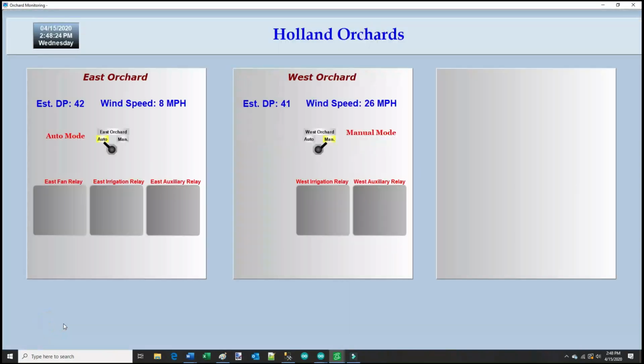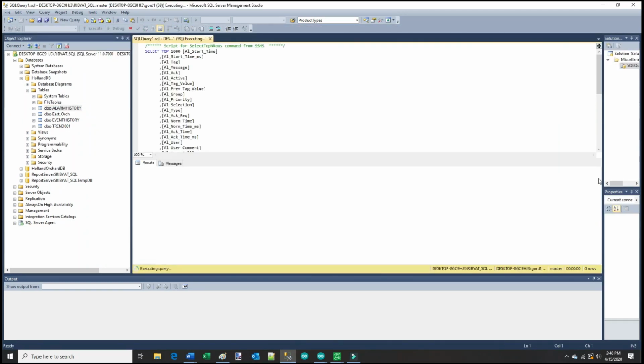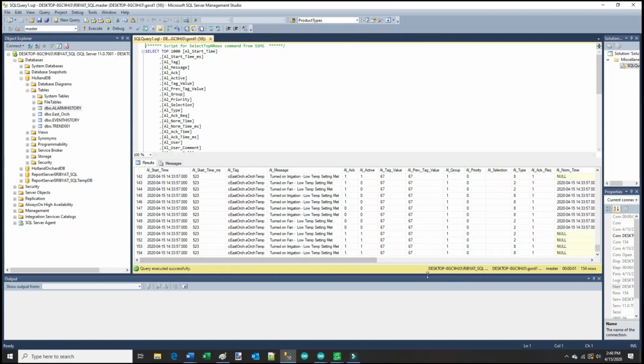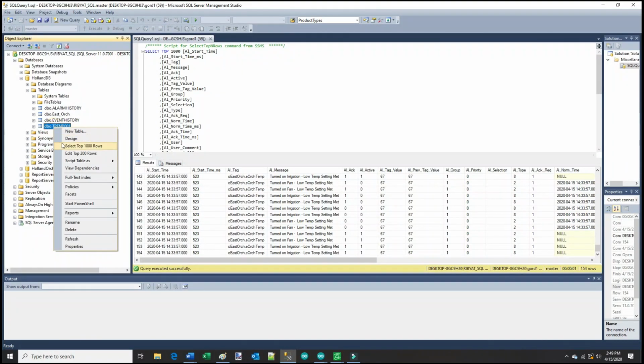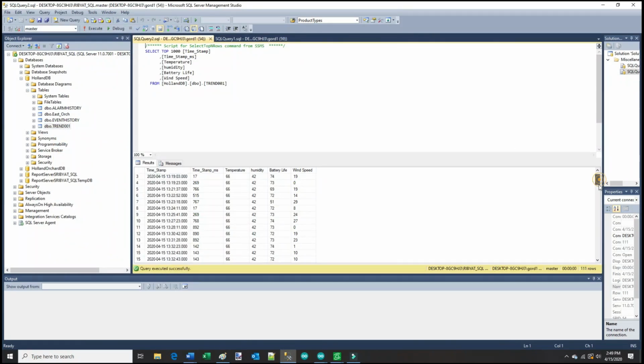So I close this. And if I open up my SQL database and show top 1000, this is my alarm history. And come down here, you can see at 2:33 I had a fan and irrigation alarm. And then if I open up my trending, top 1000, again, you can see at 2:47 I trended these temperatures to my database: wind speed, battery life, humidity.